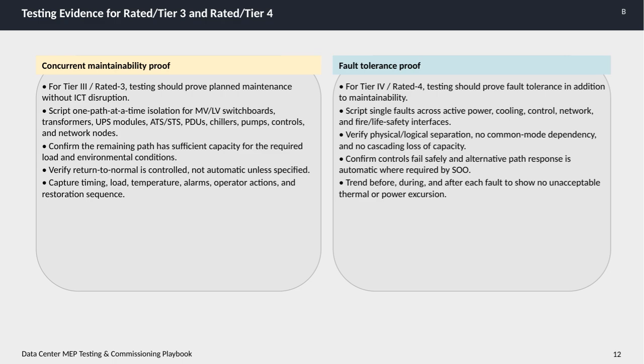During this isolation, it's important to confirm that the remaining active path can handle the required load under the given environmental conditions. Additionally, the return to normal process should be controlled carefully. It shouldn't be automatic unless specifically allowed. Detailed records should be captured throughout testing, including timing, load, temperature, alarms, operator actions, and the exact sequence of restoration.